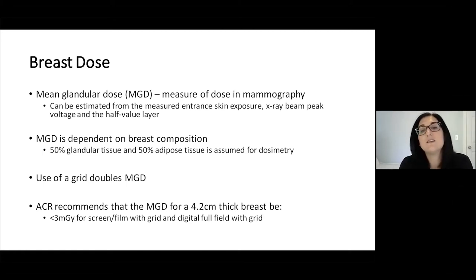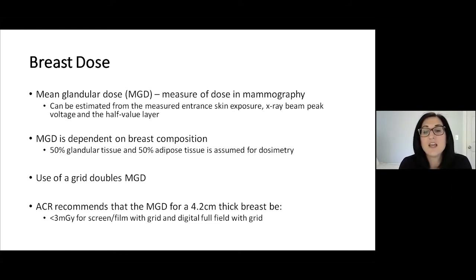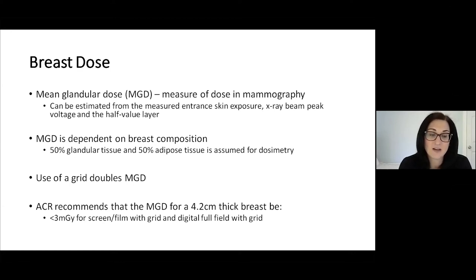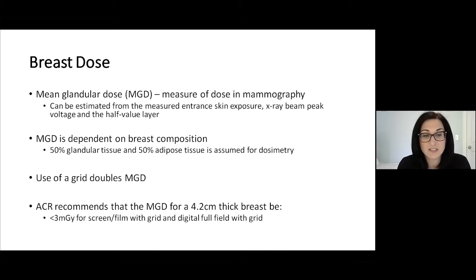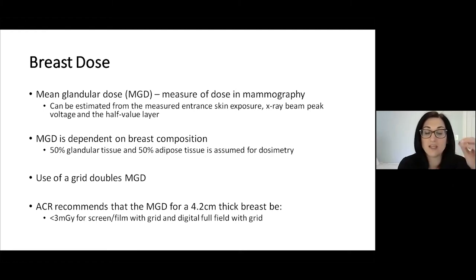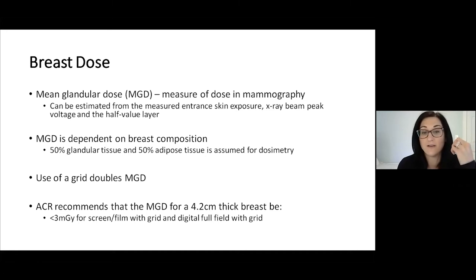Mean glandular dose is the measure of dose in mammography, and it can be estimated from the measured entrance skin exposure, x-ray beam peak voltage, and half value layer. Mean glandular dose is dependent on breast composition — if you have a fattier breast, your mean glandular dose will be different than someone with an extremely dense breast. The standard measurement is based on a breast that is 50% glandular tissue and 50% adipose tissue for dosimetry.